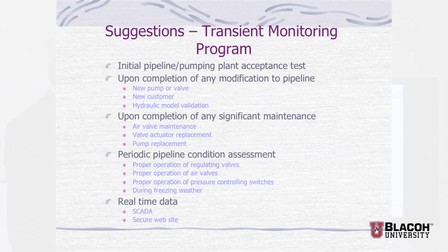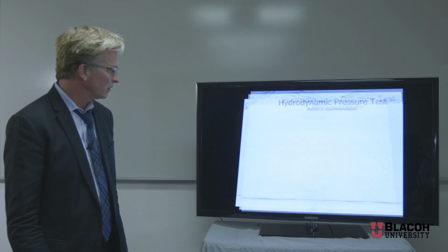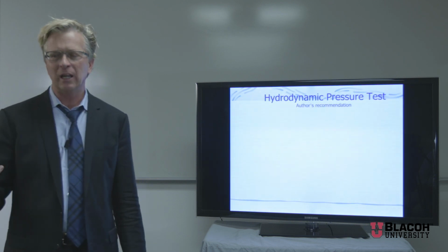So again, we look at air valves, making sure the air valves are functioning properly and that the input data into the surge analysis is correct. Of course, valve operator speed and the pump, and you can see the wear and tear on the pump. We can also hook this up to a remote location and put in a cellular dialer so we can call up the data remotely.